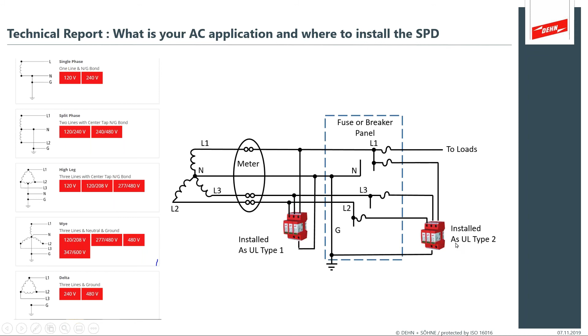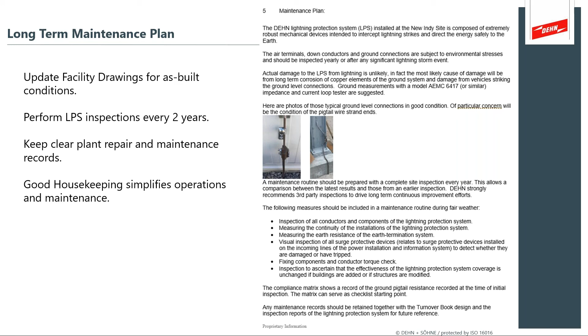In closing, we just like to make sure customers have a good long-term maintenance plan. Facility drawings should be updated for as-built conditions. You want to perform an LPS inspection every two years. Inspections from agencies such as Underwriters Laboratory or the Lightning Protection Institute are valid for two years, so it's important to come back. The apparatus are generally very robust, but they are subject to wear and tear, and it's really good to maintain proper housekeeping. It simplifies all of your other operations and maintenance functions.